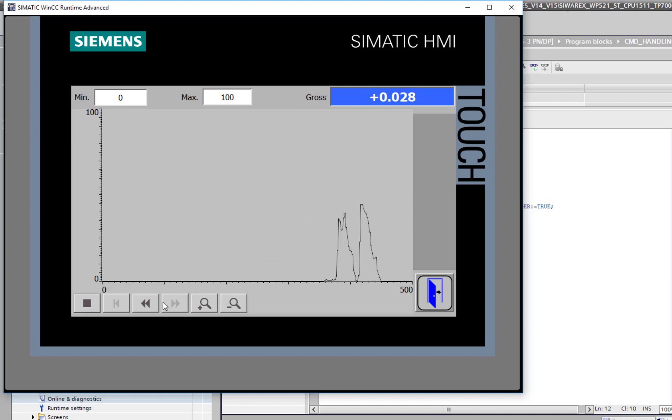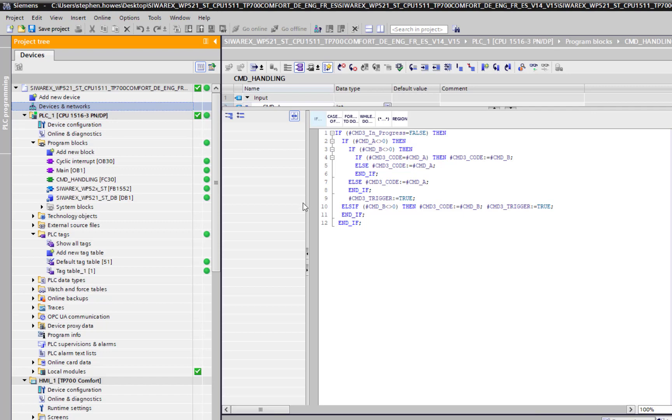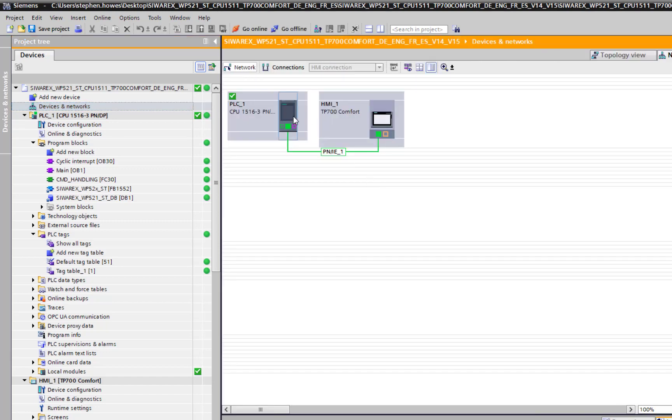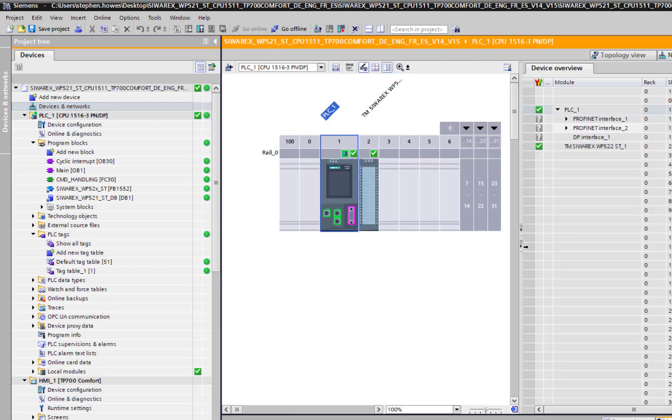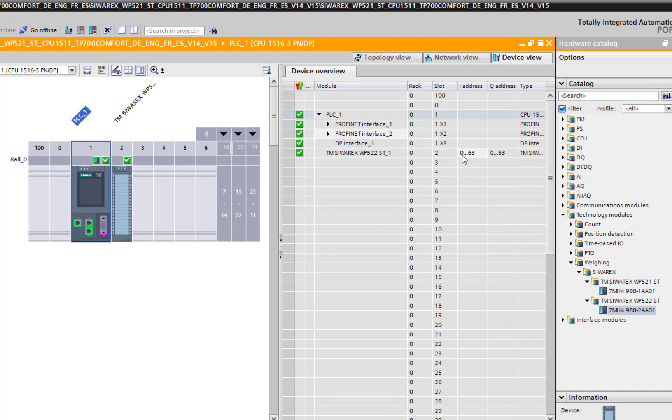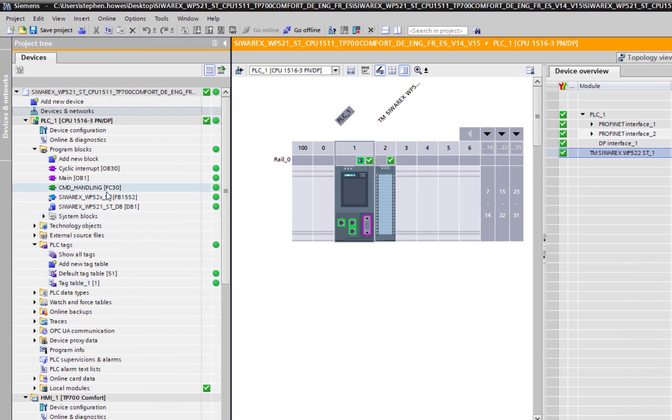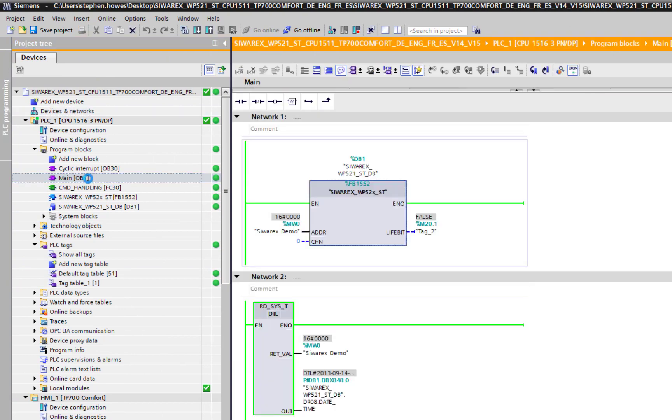Let's summarize how we've got that up and running for one scale. What we need to know is our start address, in this case it's address zero. Make sure it's in the peripheral main memory area. If it's outside of that then it's not going to work. Give it a tag, put in the tag table, spend a bit more time than what I have.